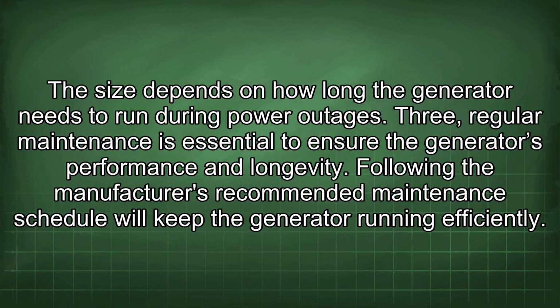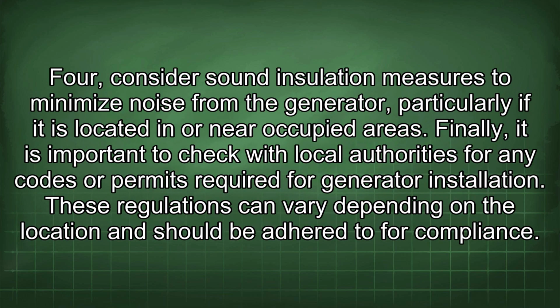3. Regular maintenance is essential to ensure the generator's performance and longevity. Following the manufacturer's recommended maintenance schedule will keep the generator running efficiently. 4. Consider sound insulation measures to minimize noise from the generator, particularly if it is located in or near occupied areas. Finally, it is important to check with local authorities for any codes or permits required for generator installation. These regulations can vary depending on the location and should be adhered to for compliance.